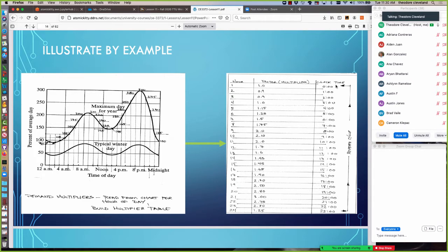various factors, and here they're shown as clock time. So at midnight, clock time 0, the multiplier is a 1. At 1 a.m., the clock time 1 a.m., second hour simulation, the multiplier is 0.9, 0.91, and so on. So we're taking that curve and we're replicating it as a table of factors.